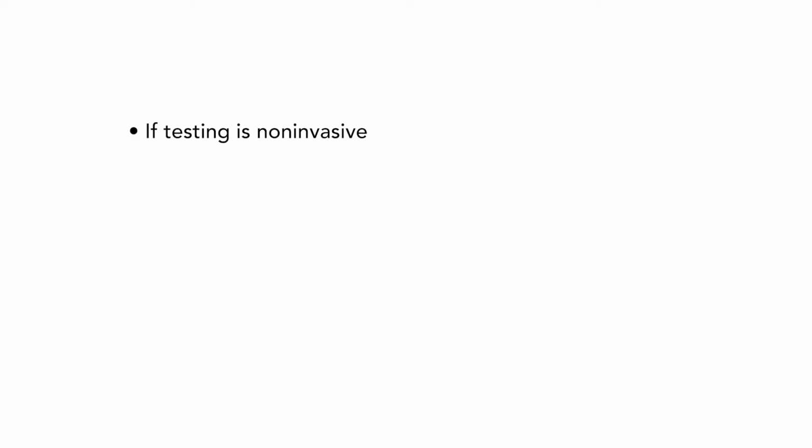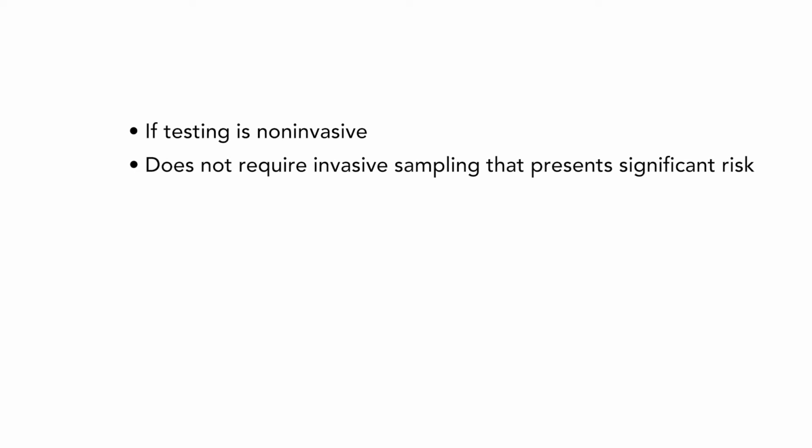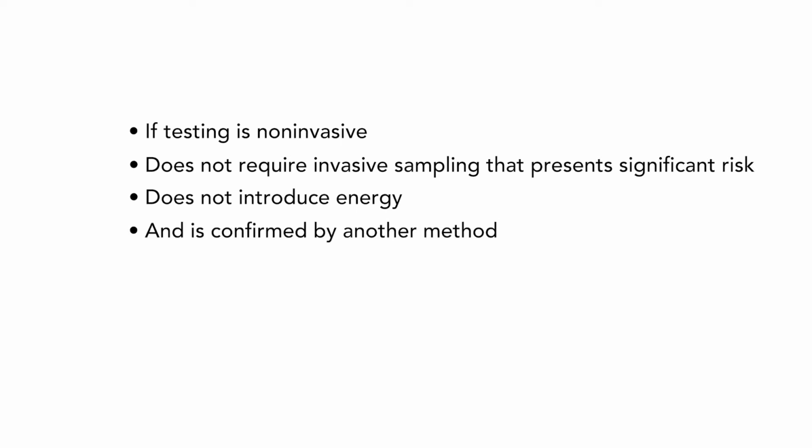Is testing non-invasive, does it not require invasive sampling that presents significant risk, does it not introduce energy, and is it confirmed by another method? If you cannot answer yes to all the criteria for testing, then your diagnostic device may not be exempt from IDE regulations, and you will need to make a risk determination. A significant risk device will require an IDE, and you will still need to obtain local IRB approval before your clinical trial may begin. If you determine that your diagnostic device is non-significant risk, then the IRB will act on behalf of the FDA to monitor your study as an abbreviated IDE.